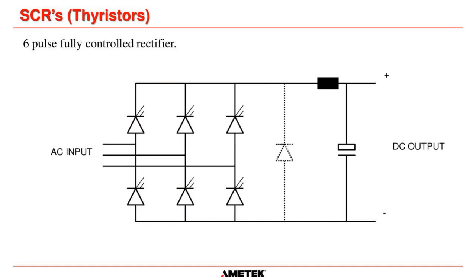And once again, let's do A phase, B phase, C phase. Let's say A phase is more positive than B phase, and we want to turn the SCRs on for those respective phases. So that would be this SCR here, because we would go out through that way, back through our loads, and we want to get to B this time. So that would be this SCR, and we would go up that way and get back to B. And depending on when we turned both of those SCRs on in the sine wave, that would depend on how much power gets through. And that's what this diagram shows you here.